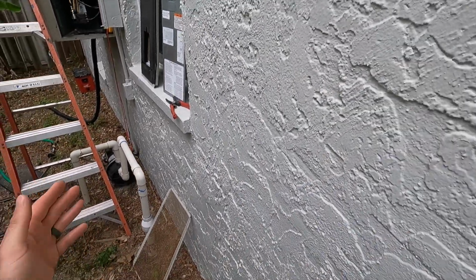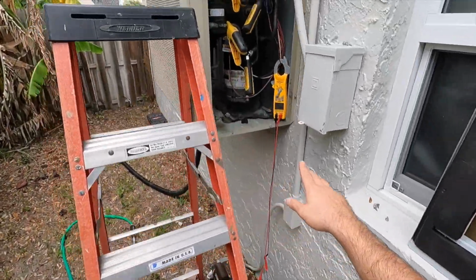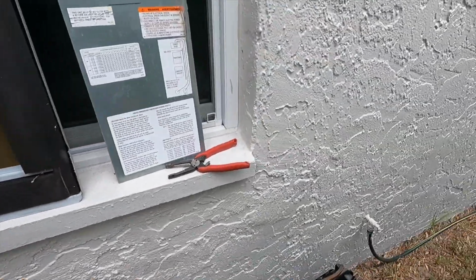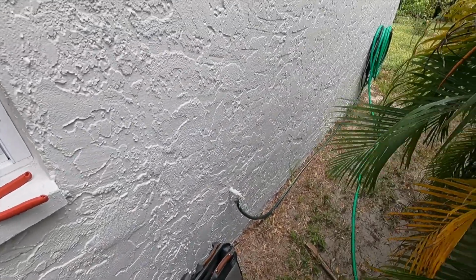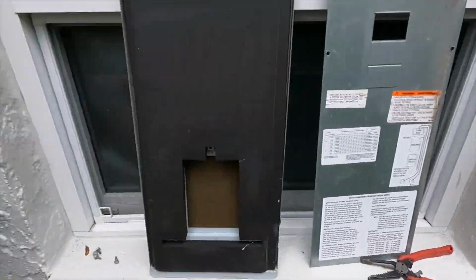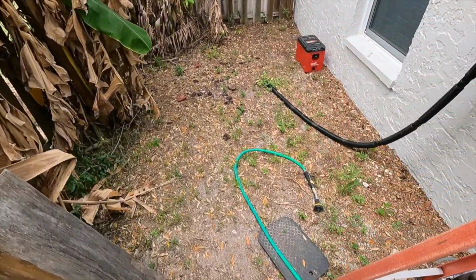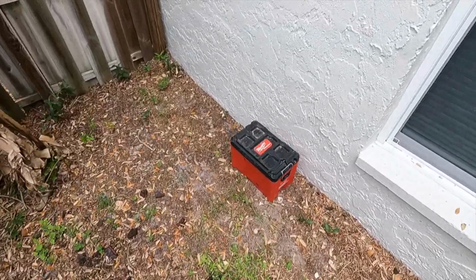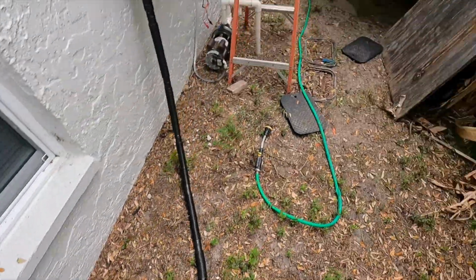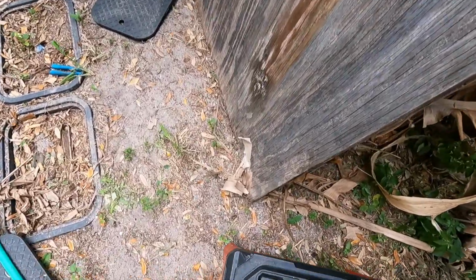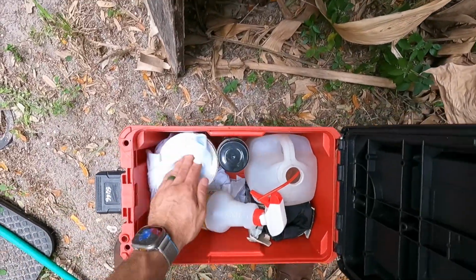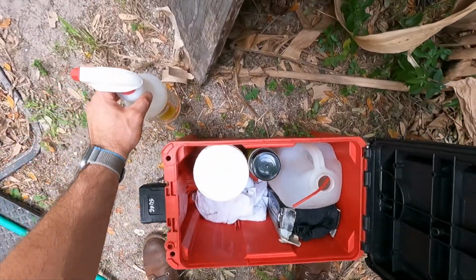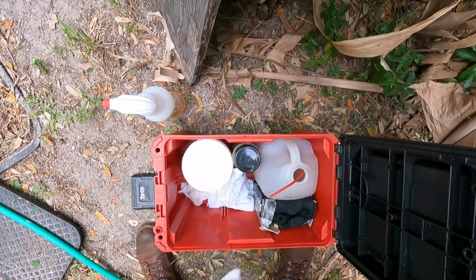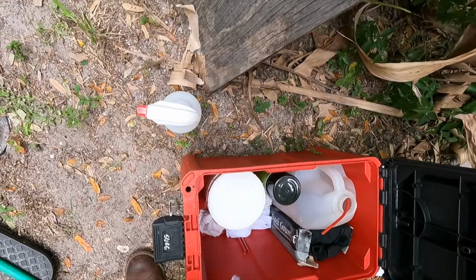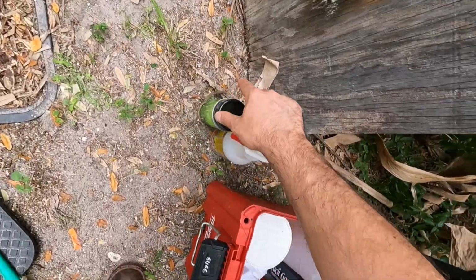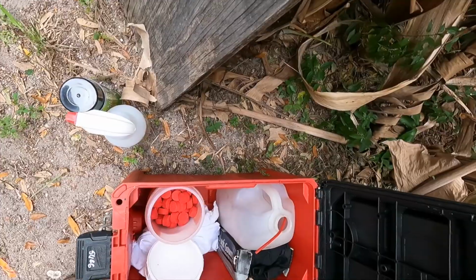So while I'm waiting on that, because I have that inrush feature on my multimeter, I don't have to sit here and stare at it and wait to catch that load intake. What I can do is go ahead and get myself prepped for the maintenance side of this, the cleaning side of this. So got a nice water hose here that we're going to get going for the condenser coil cleaning. I'm going to go ahead and get all my stuff for my actual maintenance of the blower, the evaporator coil, and the drain pan ready to go. So we're going to throw some algicide tabs in there.